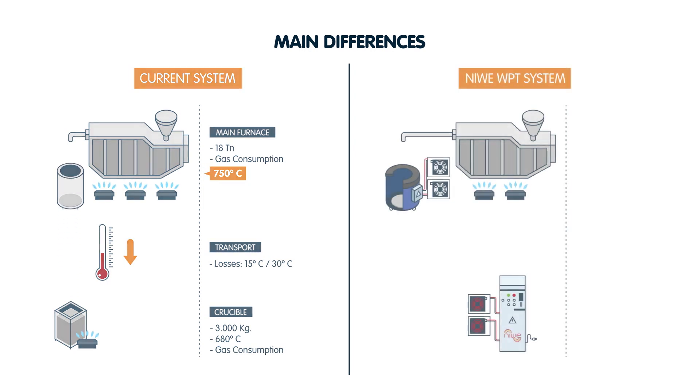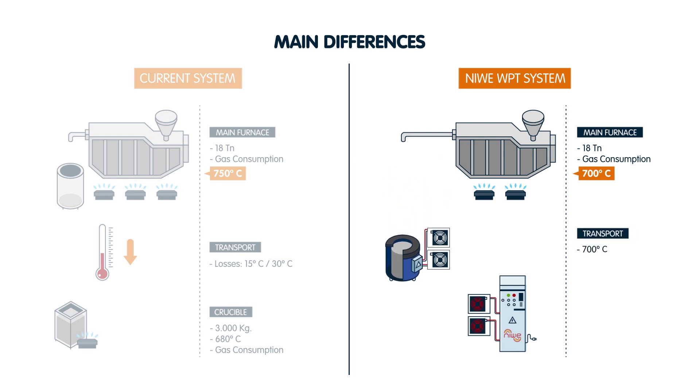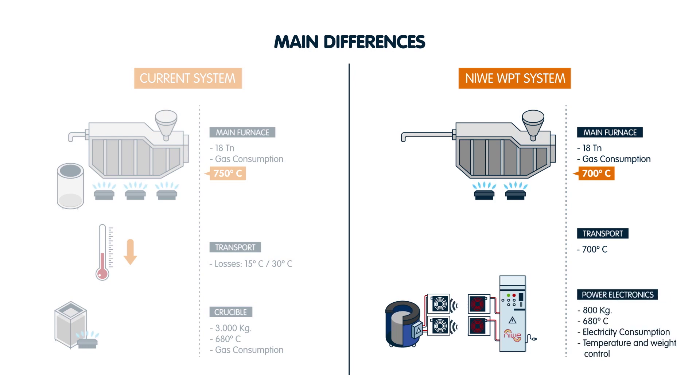With the NIWE WPT system, production temperature is reduced to 700 degrees centigrade, requiring less initial energy. In addition, since the line crucibles are mobile, heat losses are minimized in the transport and pouring process. Once in the line, the system offers better temperature control.